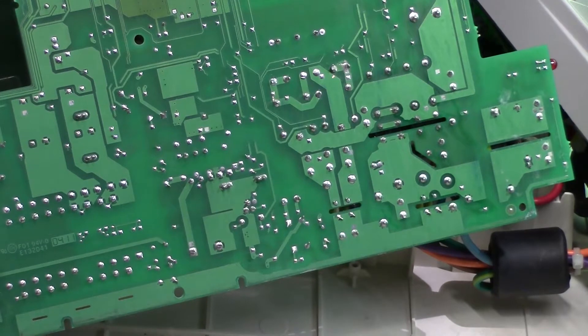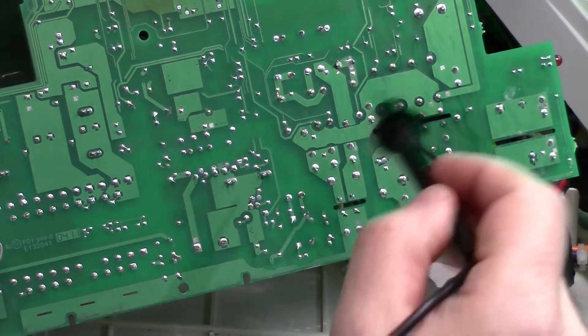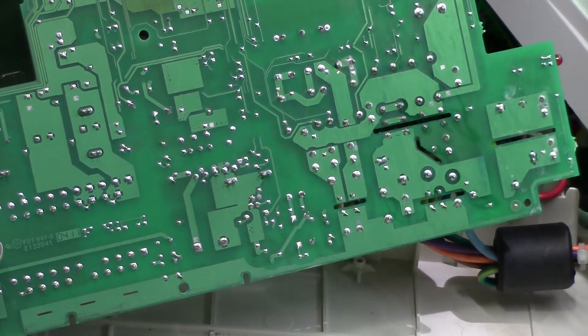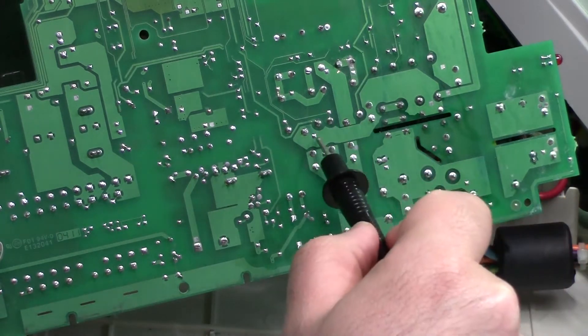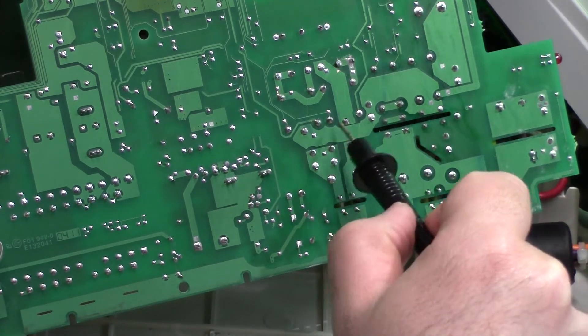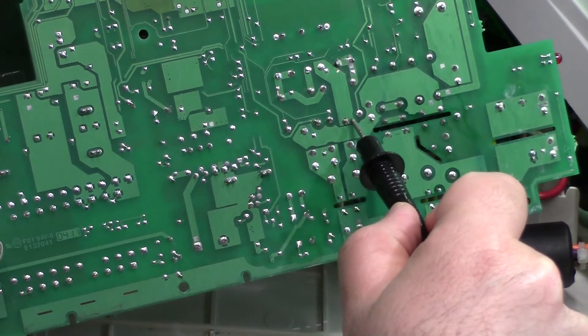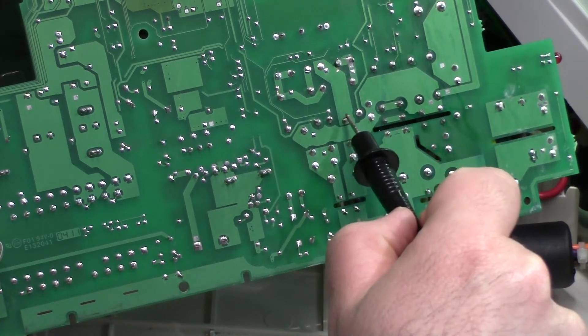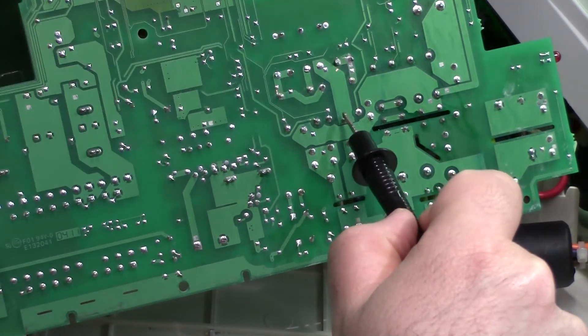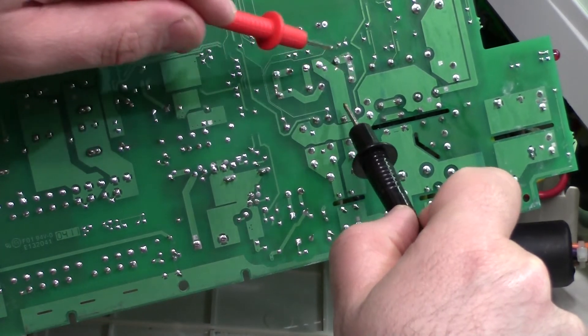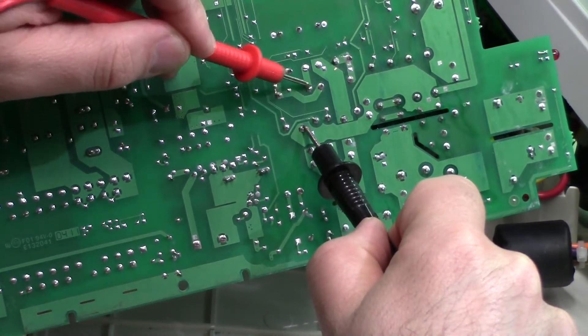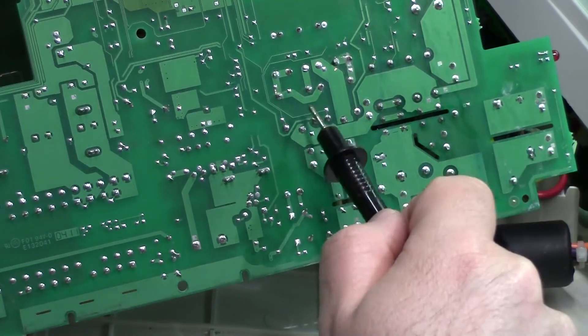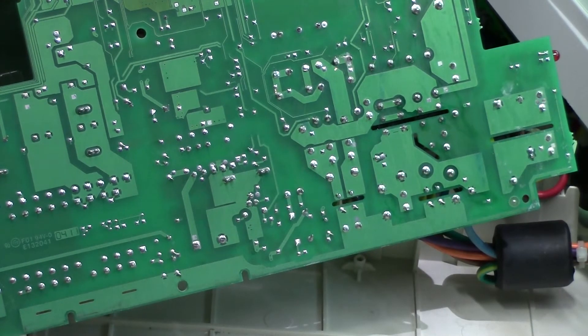All right, so I've been in some trouble shooting with this. And I've confirmed that the inverter does actually work properly. I was able to find 116 volts. But it appears that one of the relays has actually gone open, which is really weird. If we look at the back of this, it's a bit hard to see. But basically, we've got one relay assembly here, and another relay assembly over here. You can kind of see it. Here are the two coil inputs here. And here's the actual input. That's dual-throw relay. And out here, you have the two outputs. Well, if I measure this one, you can see in its default state. I'll settle deeper. In its default state, we've got continuity from here to here, which is normal. If I measure the trim relay right beside it, across this terminal and this terminal, it's coming up as open. So this relay must have gone bad. And the 1.5 volts I was seeing was probably just some capacitive coupling.